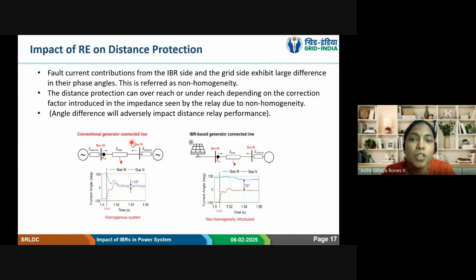So what happens here is the fault current contributions from the IBR and the grid exhibit a large difference. What happens in a conventional system? When a fault occurs, both the sources are contributing. And if we compare the angle between these two sources, it is relatively low, less than 10 degrees. Whereas when we have an IBR and the other end source, the angle between the sending and receiving end depends on the control of this IBR, and it can vary. There can be a larger variation in the angle.